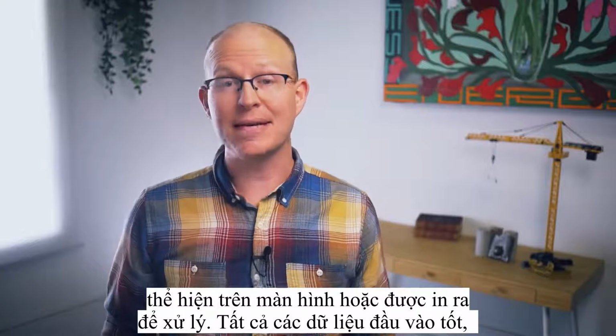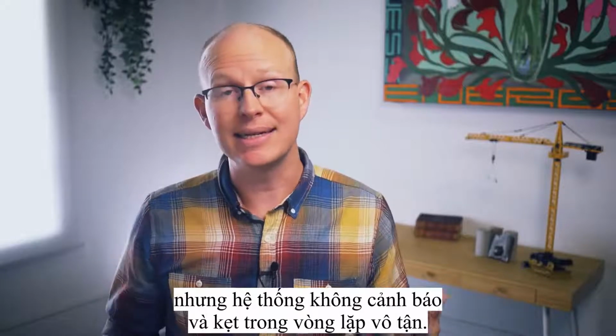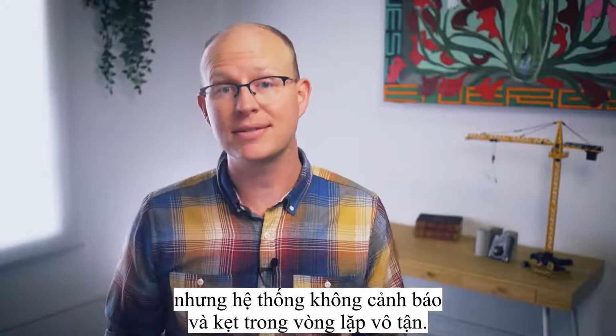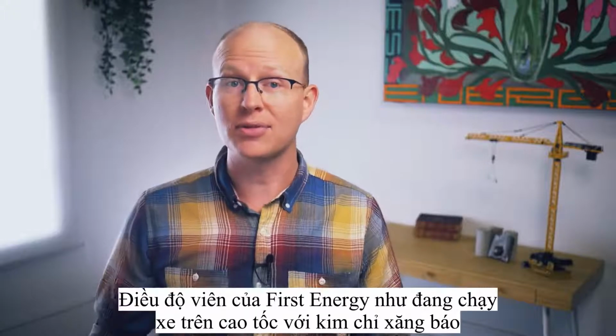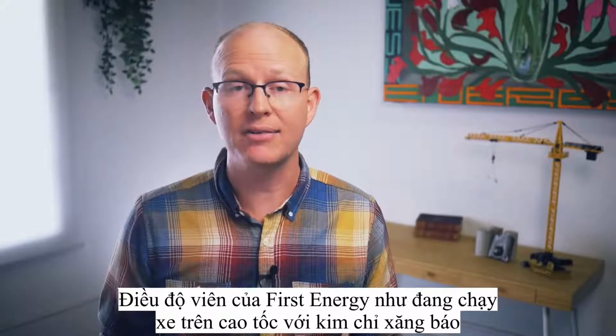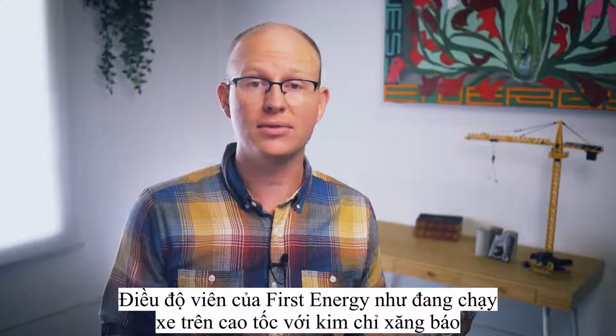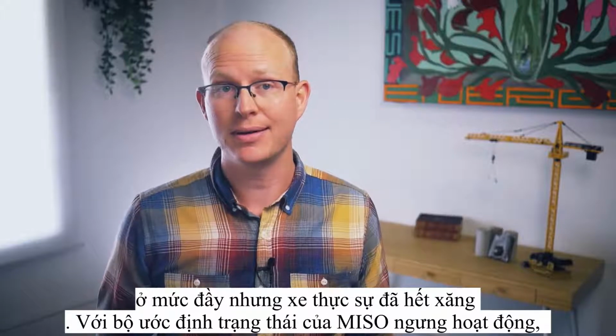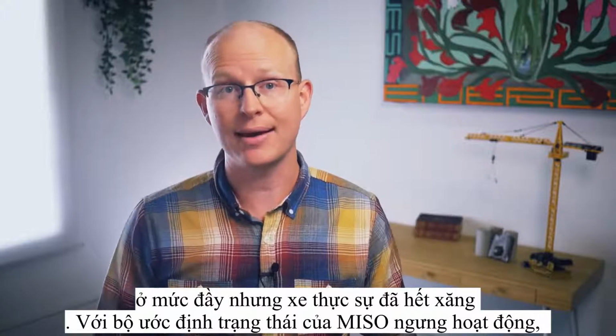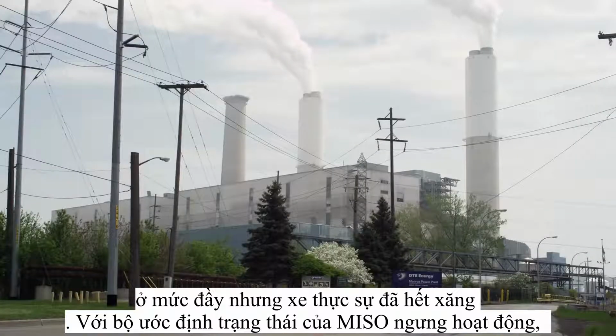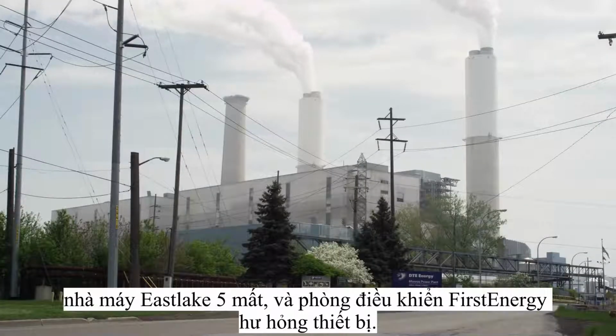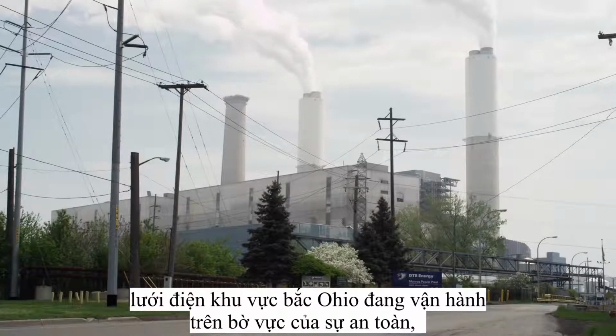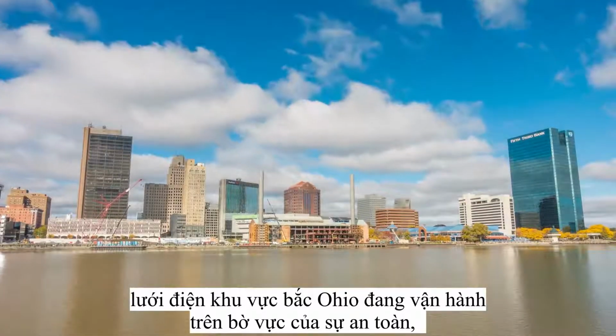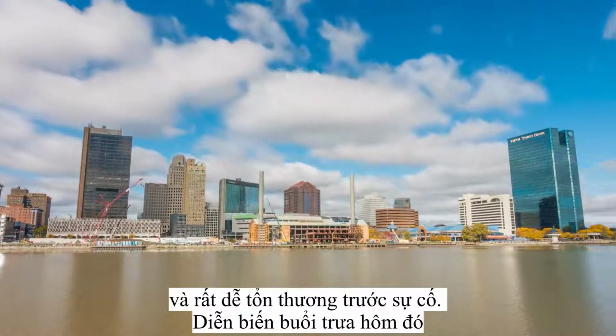All the data was coming in, but the system, designed to get an operator's attention, was stuck in an infinite loop. The First Energy operators were essentially driving on a long country highway with their fuel gauge stuck on full, not realizing they were nearly out of gas. With MISO's state estimator out of service, Eastlake 5 offline, and First Energy's control room computers failing, the grid in northern Ohio was operating on the bleeding edge of the reliability standards, leaving it vulnerable to further contingencies.